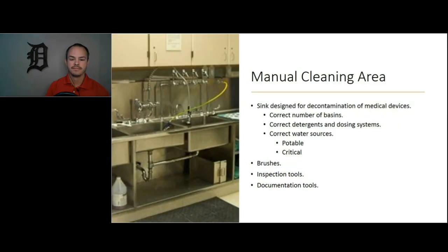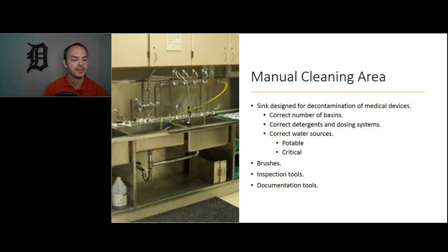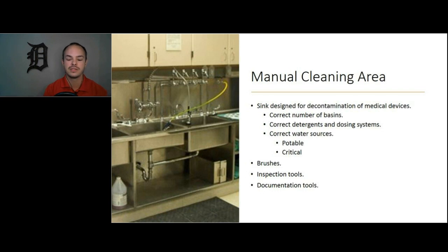Consider the manual cleaning area. Does your sink have the correct number of basins? Does it have the correct detergents and dosing systems? What about the source for critical water? We can't forget about brushes, inspection tools, and other necessary items. Maybe your decontam at an ASC is the size of a closet — that's a problem. You need adequate space to do your decontam duties, the right air exchanges, and the right air pressure. You need all of those things to do it right.